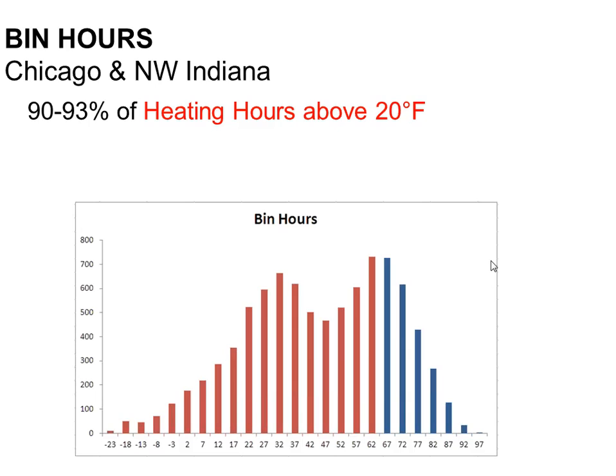This just shows you pictorially how many heating hours are at each incremental step. This little chart goes in 5-degree increments. For example, right here I'm at 12 degrees. I have 300 hours that are near the 12-degree mark, so from 10 to 14 degrees or something like that. If I look a little further, I have a good amount of hours in the high 20s, low 30s. And then I have a ton of hours here that are in the 40s, 50s, and 60s.